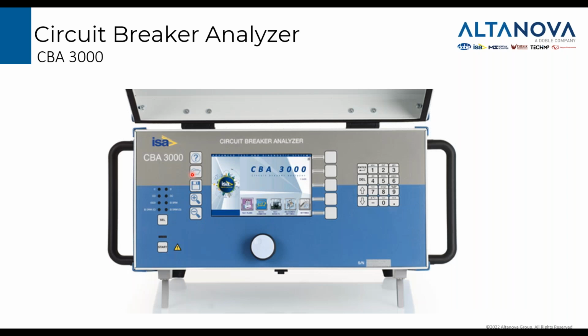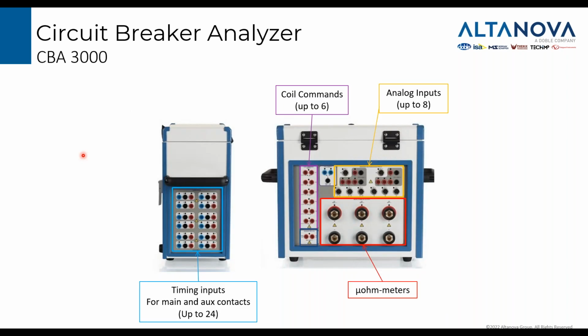If you want to do a test, it's possible to, for example, use a CBA 3000. It is a device designed exactly for these purposes. It is provided with several digital inputs for the time measurement of main and auxiliary contacts, and it is also provided with coil commands up to 6. In case of a high voltage circuit breaker, you may have 3 independent commands for the opening and 3 independent commands for the closing. We have up to 8 analog inputs for the test.